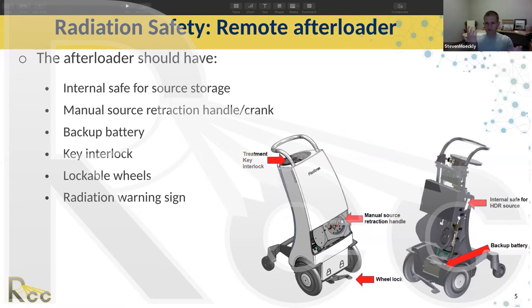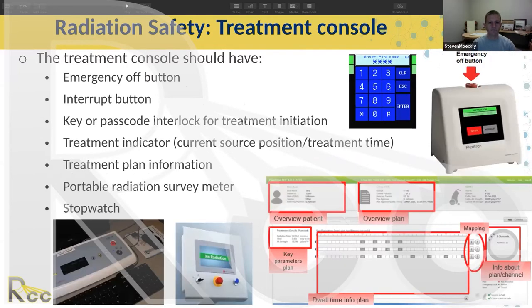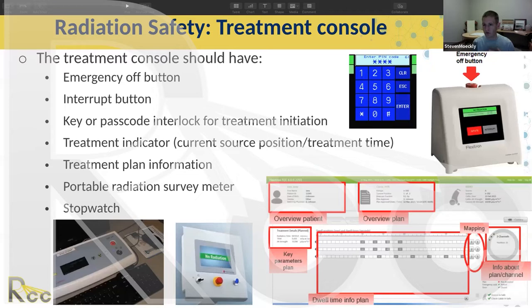You don't want the machine pulling the catheters out of the patient while you're treating. Radiation warning signs should be inside. The treatment console should have an emergency off button — test that daily — and an interrupt button, which may be digital. You need a key or passcode interlock for treatment initiation; each user should have their own unique input number or unique login so that all logins for the treatment are unique.